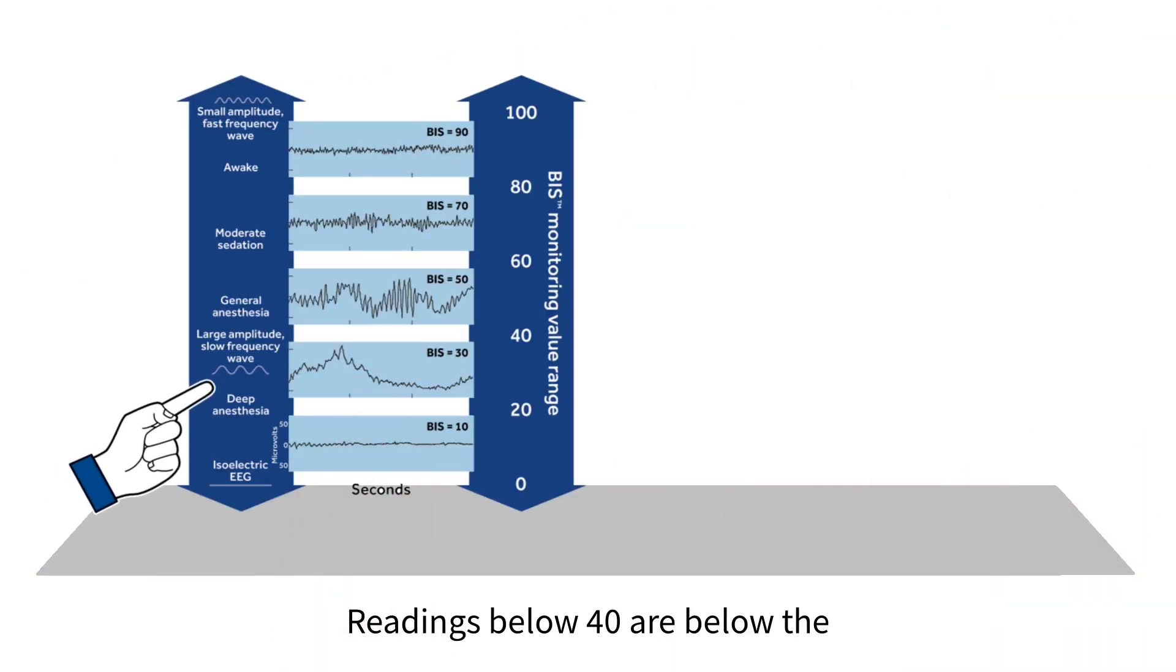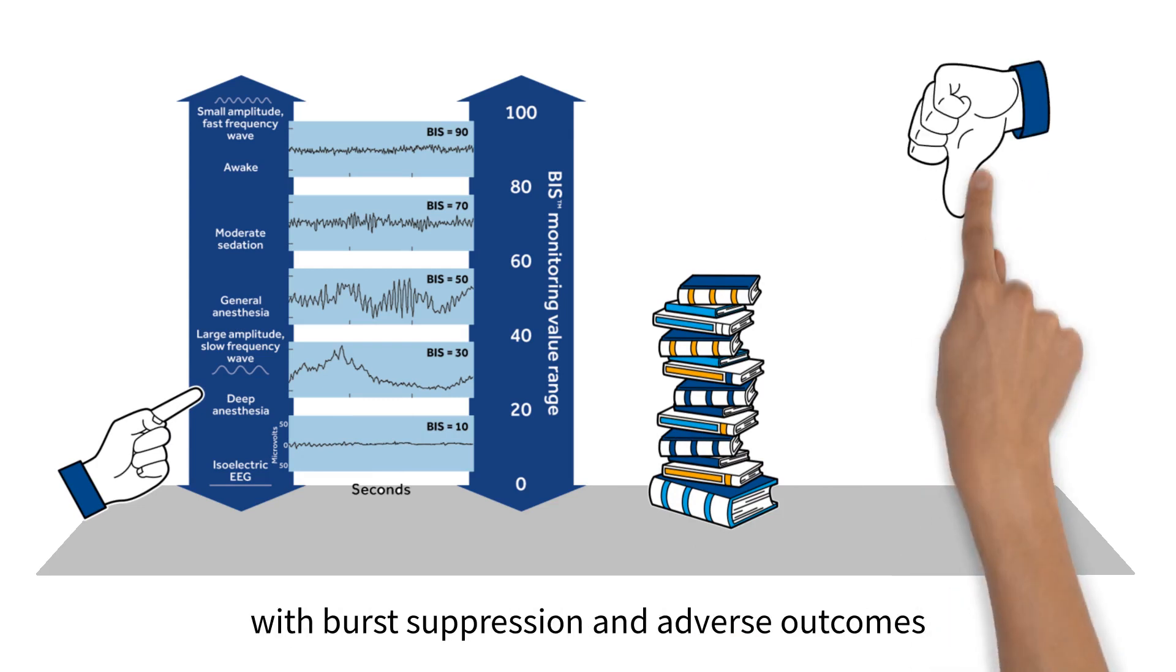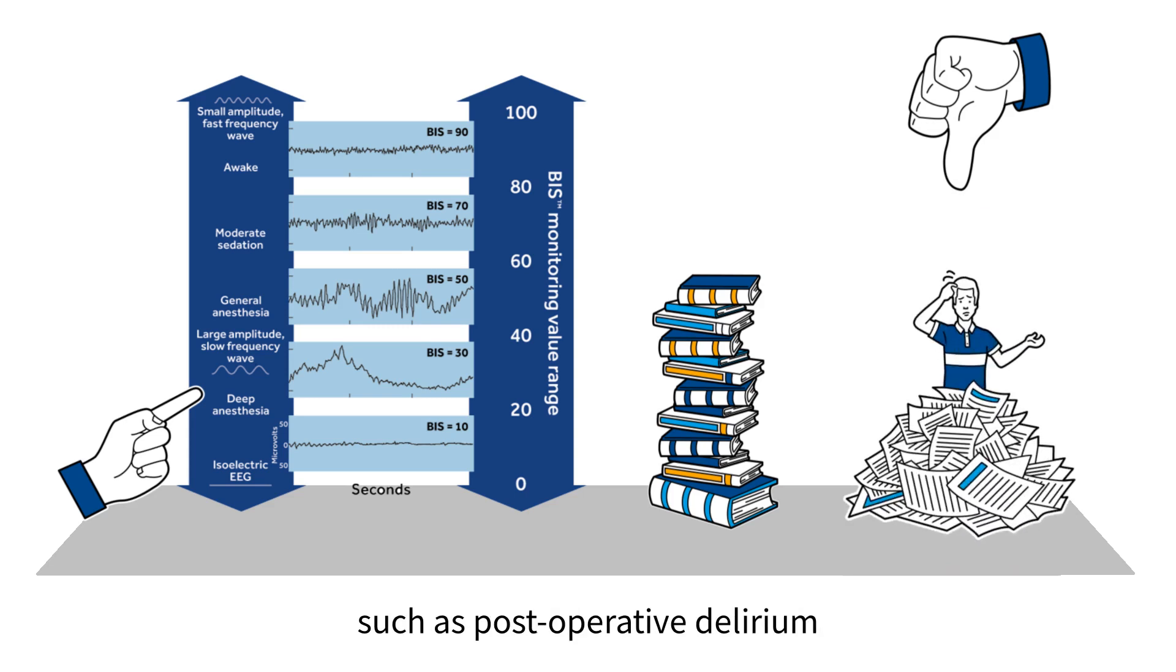Readings below 40 are below the recommended range. While these values still correspond with general anesthesia, studies indicate that unnecessarily deep levels of general anesthesia are associated with burst suppression and adverse outcomes such as post-operative delirium.